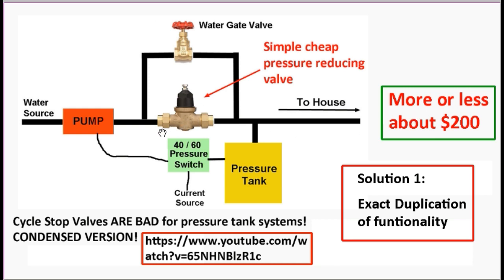Usually the cycle stop valve will have the internal leak inside, but instead of having it in here, I buy the pressure reducing valve, which doesn't have the leak, and I reproduce the leak by having this bypass. Some people got confused. They thought that every time you turn on the water, you have to turn this valve or something. No, you adjust this valve, and then after you adjust the valve, you forget about it. What the valve does is it produces a small flow that bypasses the pressure reducing valve.